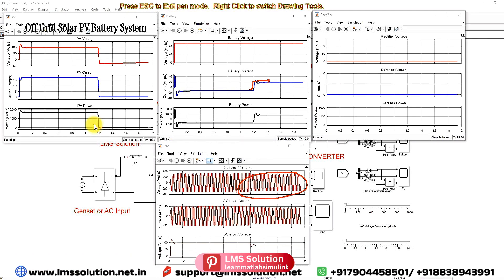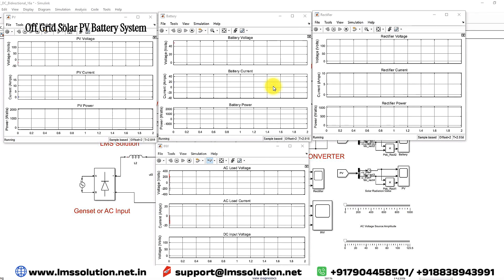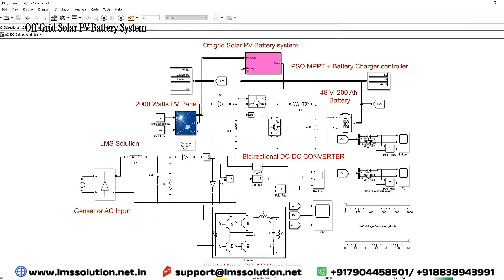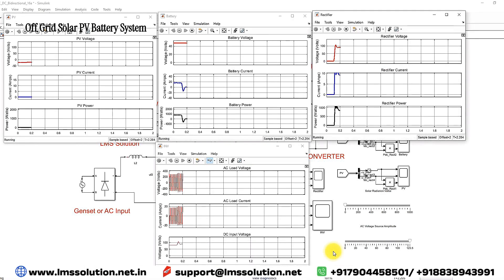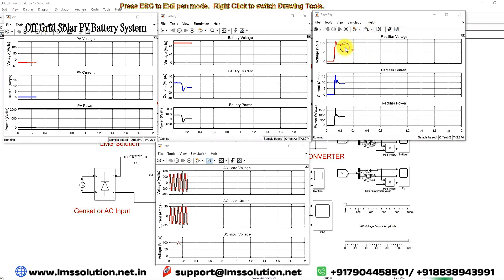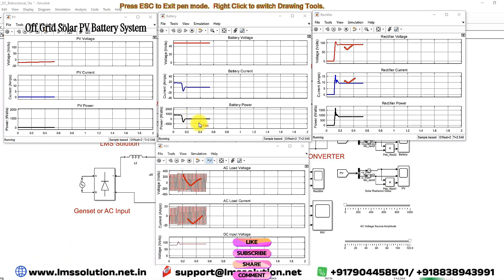Now we consider the SOC of the battery is very low, so I am going to connect the generator set. Because of the inclusion of the generator set, the rectifier voltage and current are increased. The generator set is now supplying power to the AC load, and the power generated from the rectifier/filter directly drives the AC load, so it is maintained constant.